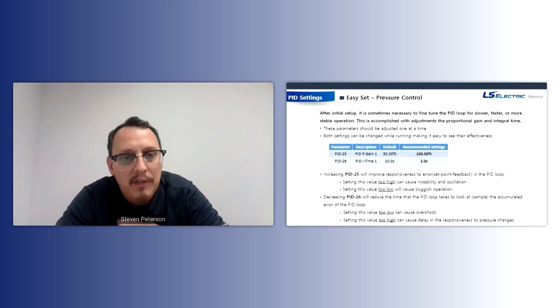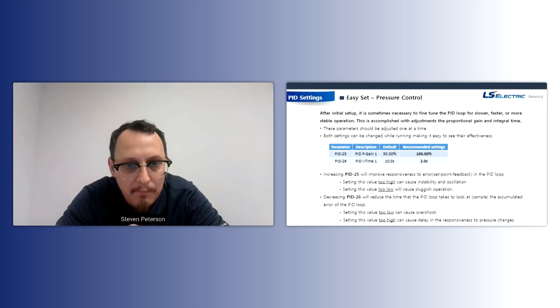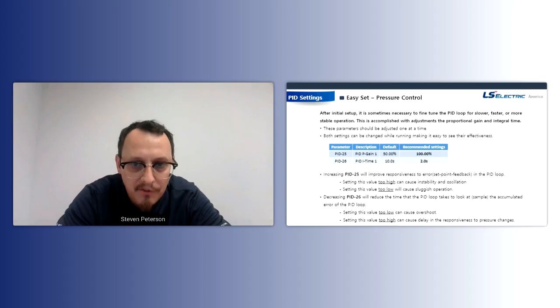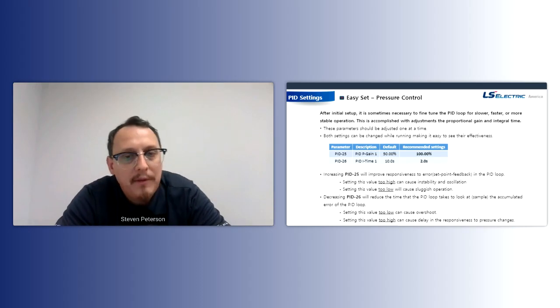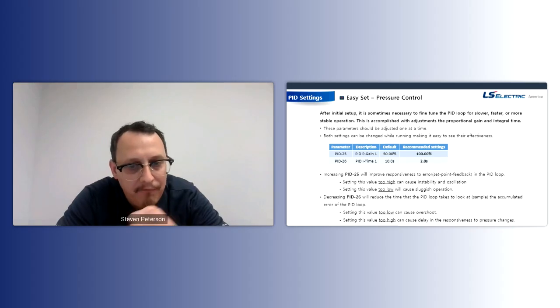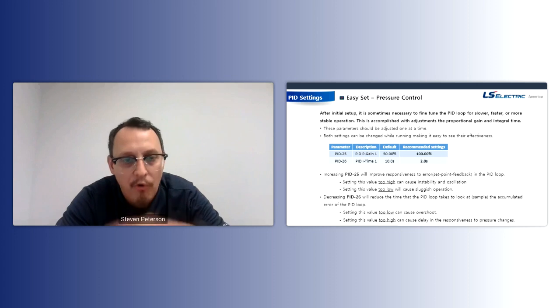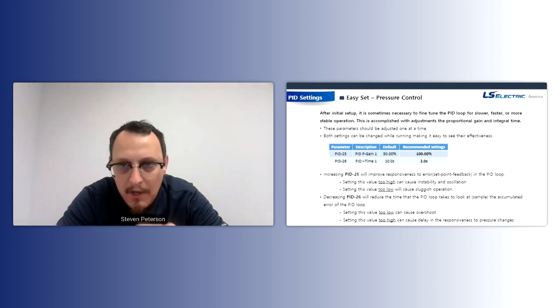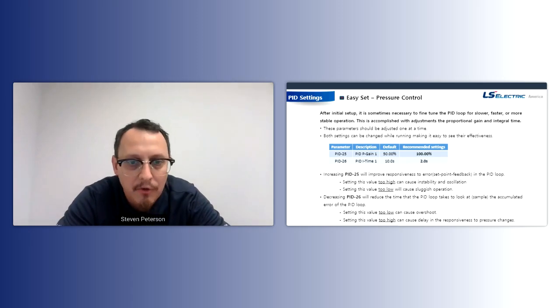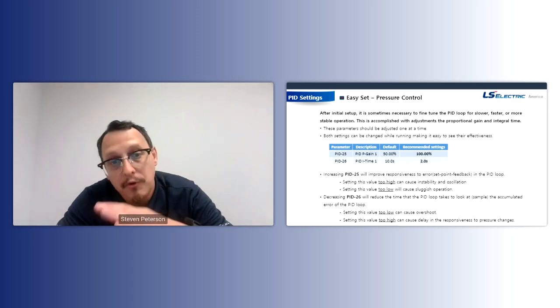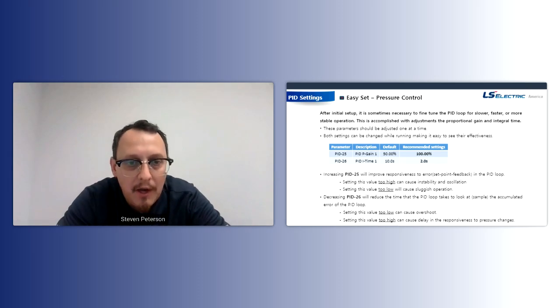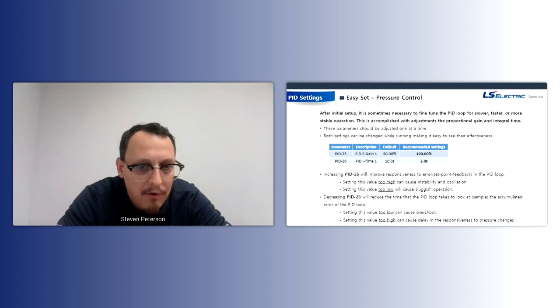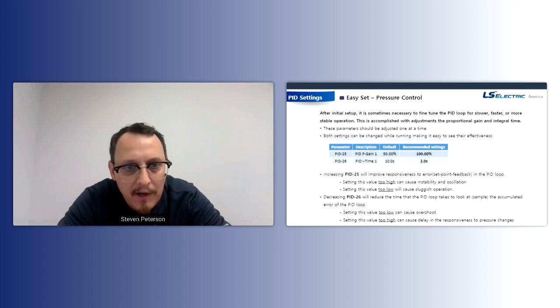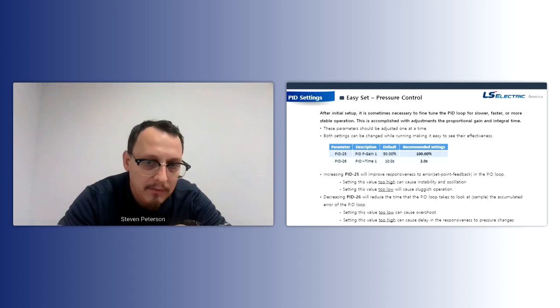The gain is kind of like a sensitivity. You're seeing how sensitive you want the response to the error to be, and the error is the difference between the set point and the feedback in the PI loop. Sometimes if you go too high, like 500, 600% or something like that, that could cause some instability and oscillation because it's overshooting. It's way too responsive. So I recommend increasing this maybe 50% or so at a time and seeing how it helps out. If you go too low, that's going to make things less responsive, a little more sluggish. But I typically start with the P gain. Next, if it's still not responding fast enough, I don't want to go too high on that P gain because then we could get some oscillation.